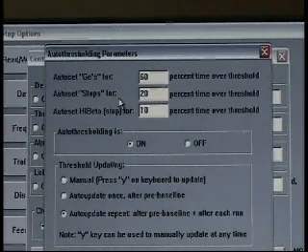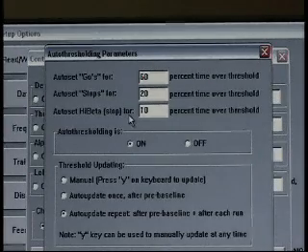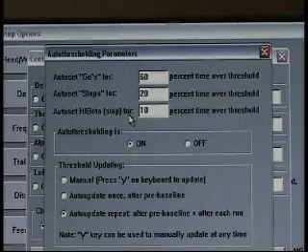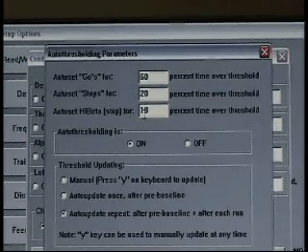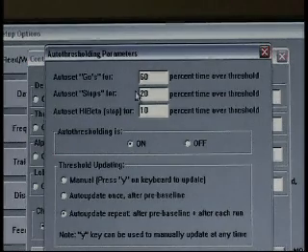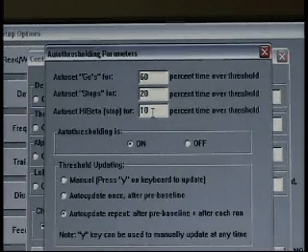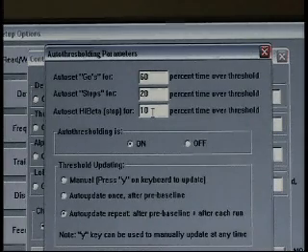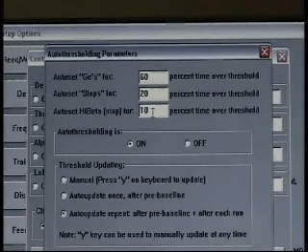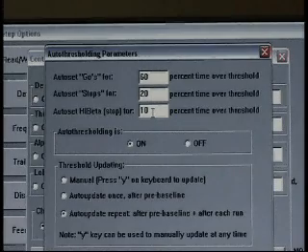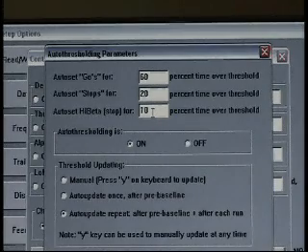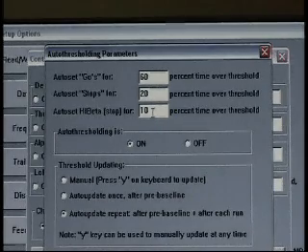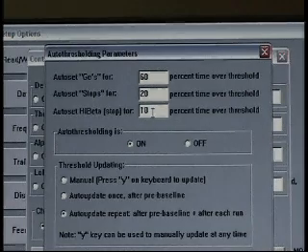We also give you an independent setting for high beta just so it can be used as a guard band, and you notice that we use 10. These numbers are all adjustable, and you can adjust them both here and from the training screen live. But currently, the goal would be for the client to meet criteria for high beta 90% of the time, because the definition again reads 10% time over threshold, and it's a stop, so we want to be below.